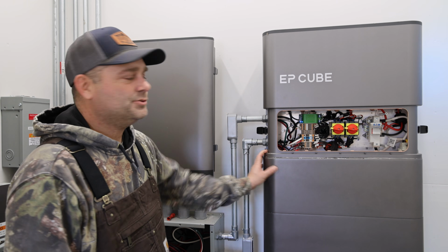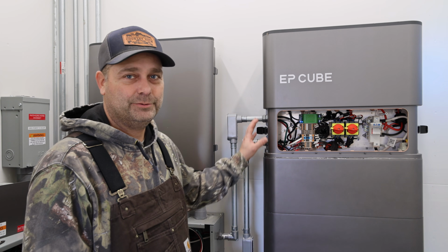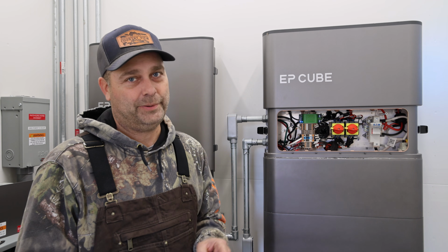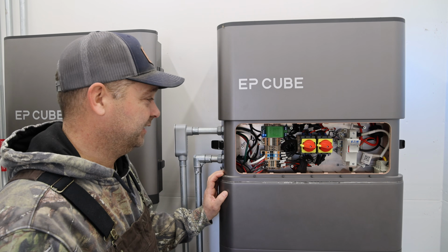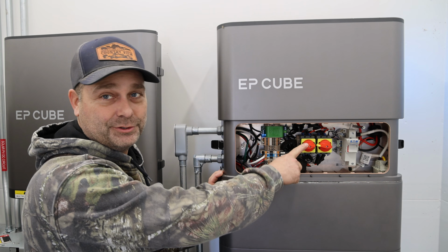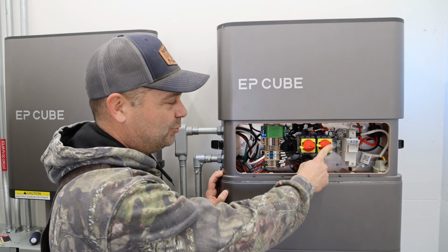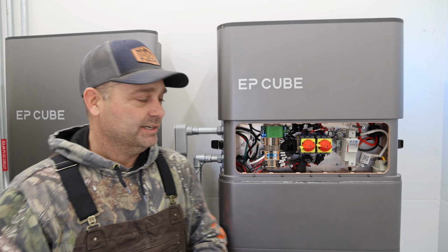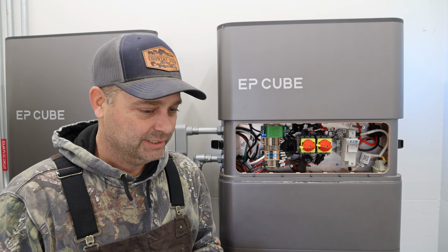But before I do, I just want to go over the problem, and I want to go through how I troubleshot it to get to the point where I knew it was the inverter and not my solar panels. So this inverter has 4 charge controllers on it, and there's 2 disconnects here. Charge controllers 1 and 2 are on one of the disconnects, and charge controllers 3 and 4 are on the other disconnect.